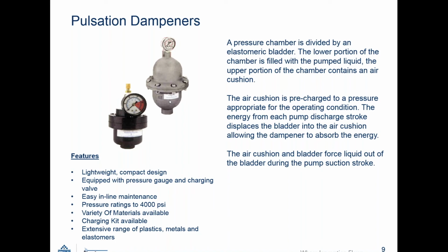They're equipped with pressure gauges and a charging valve. The charging valve is there for charging the top portion of the unit. The unit is generally charged at 80% of the discharge pressure. Easy inline maintenance. You can see that it's flanged so they can be easily removed, or the bladder can be easily removed for either troubleshooting or replacement. We do have pressure ratings up to 4,000 psi. They are limited at 4,000 psi to 12 and 24 cubic inch sizes.